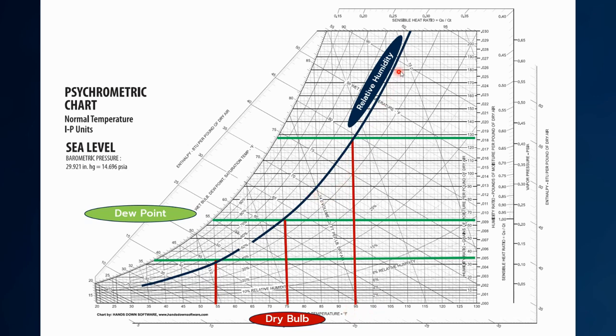Now as you can see, the relative humidity is the same value for all these three points, but the moisture content is vastly different from point one to three. That's why dew point is a much better way to measure the actual humidity that's in the air.